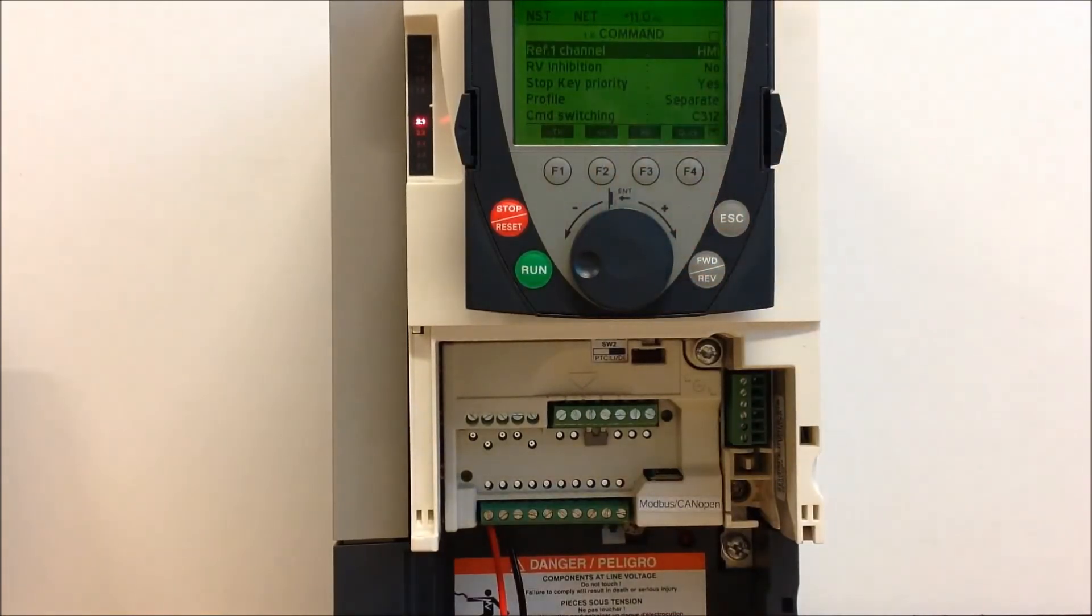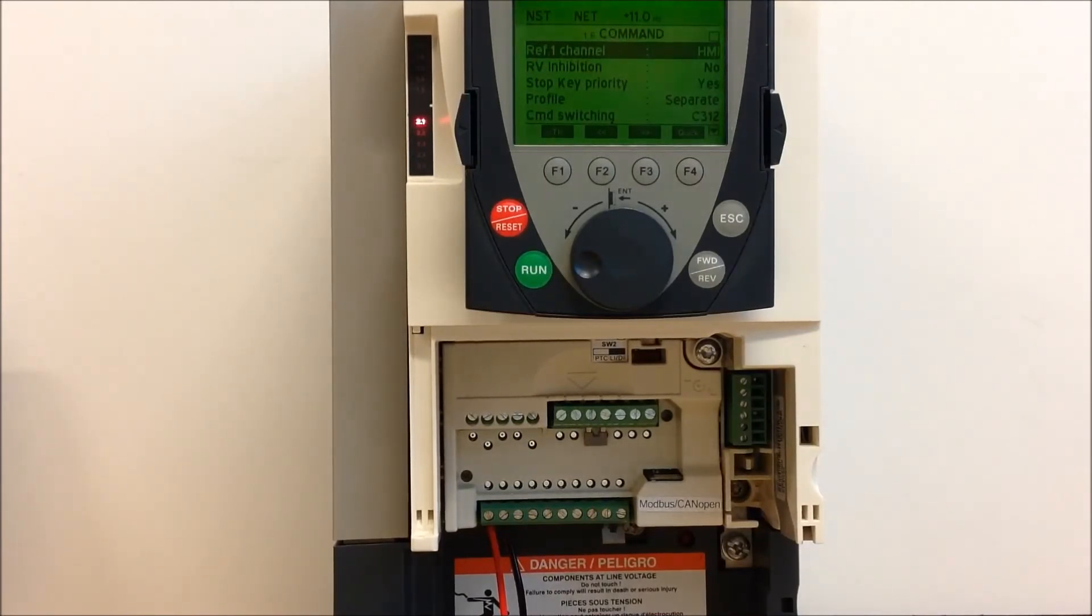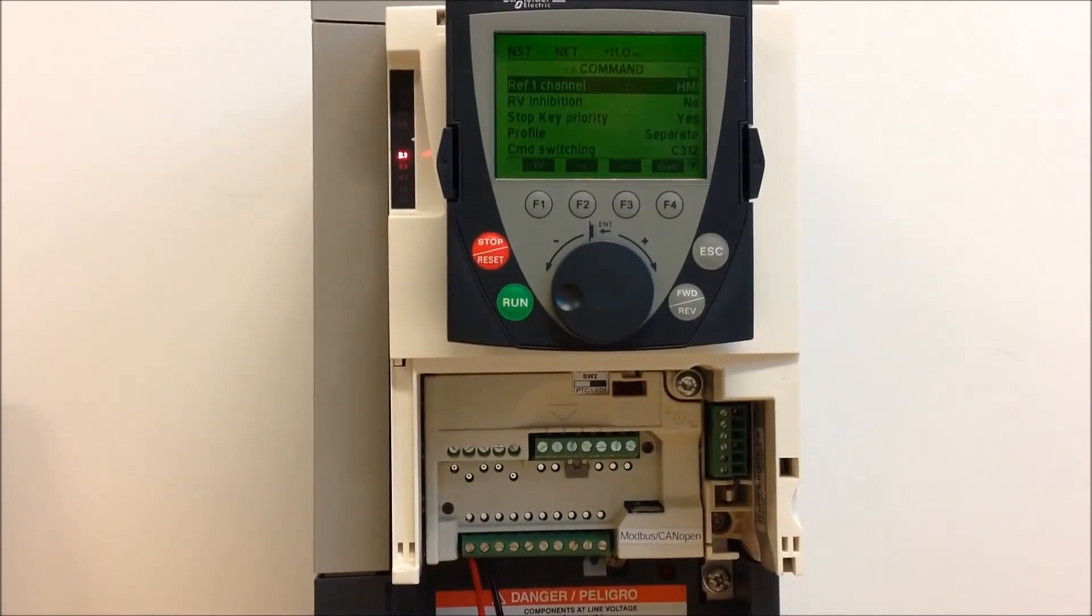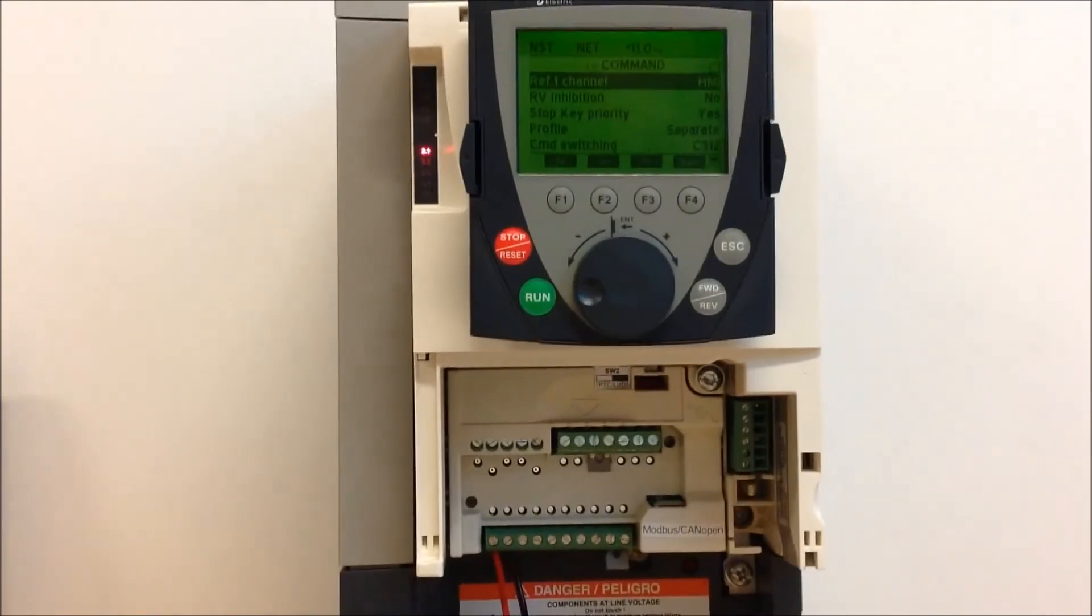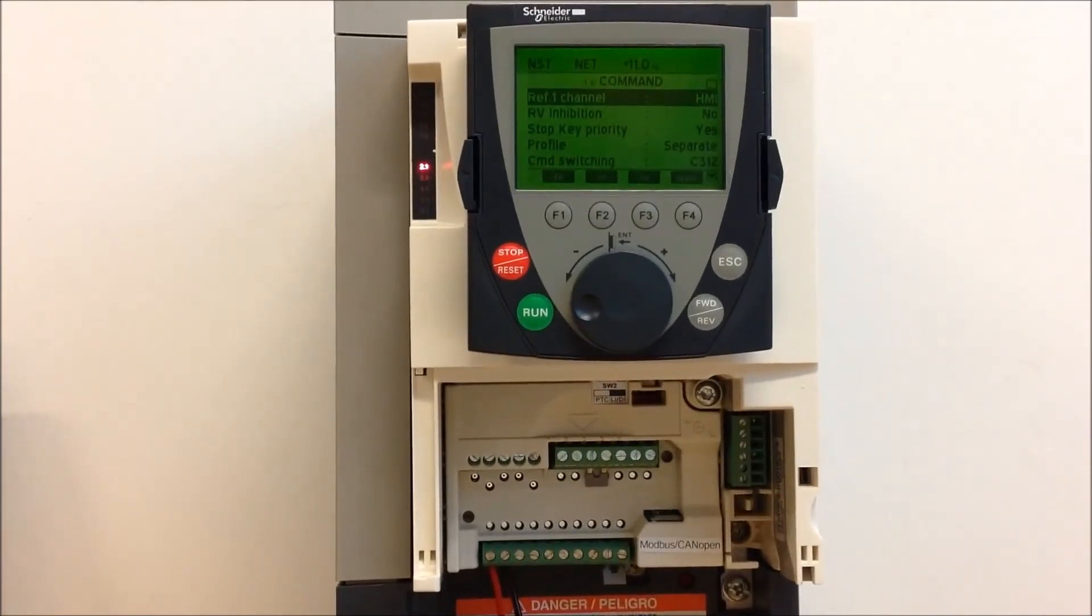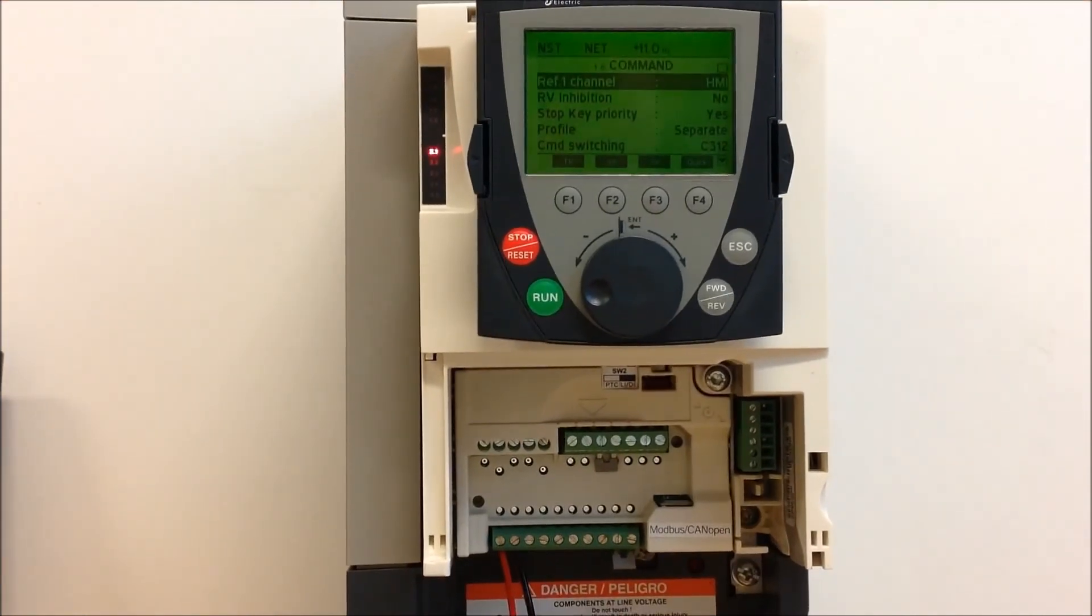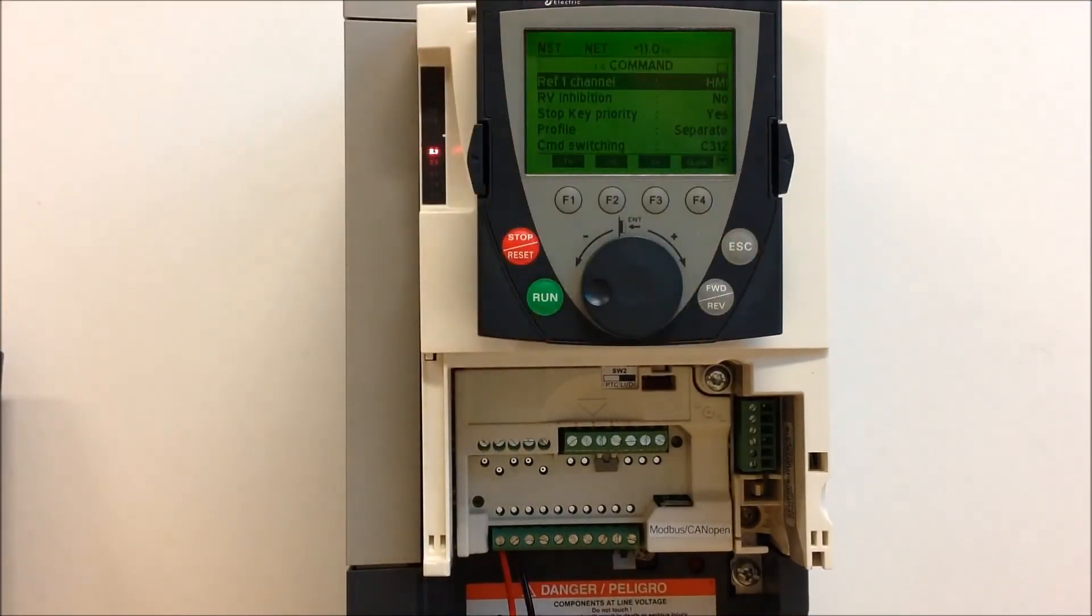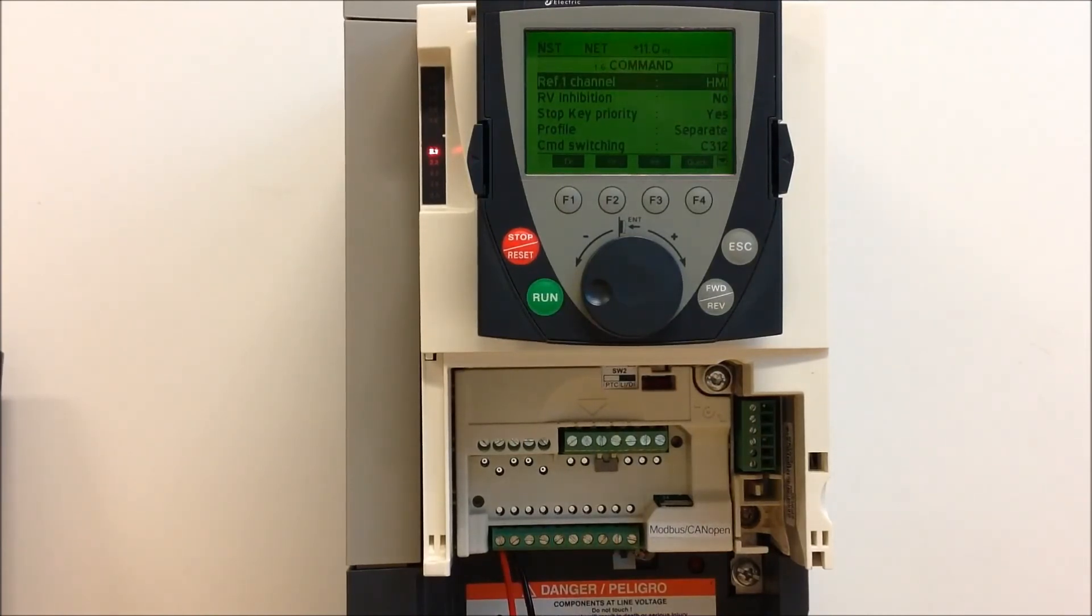So now that we have, just to confirm here, we currently have PID set up in the drive. We have the PID enabled with the feedbacks and references programmed, your ranges are programmed, and all we have done so far is allow the keypad to act as your setpoint while disabling the function where you tell the drive what your setpoint is as a parameter.